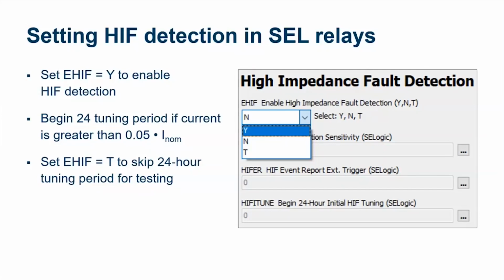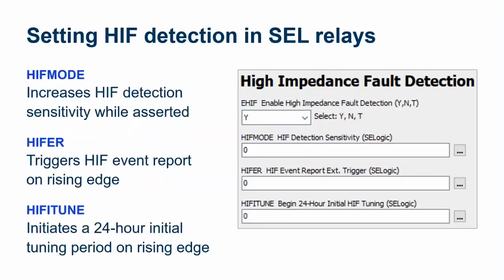We don't recommend setting it to T for actual applications out in the field. We have a few other settings here. We have a setting called HIF mode, and what this does is increase the sensitivity of our high impedance fault detection when it is asserted. This is just an SEL logic equation that you can set up to say when we should increase sensitivity. I'll talk about ways to apply that in the next few slides.